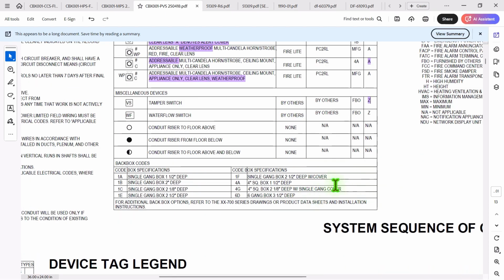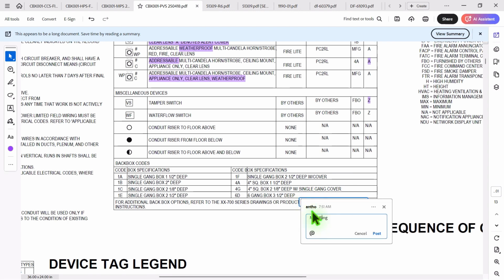Now when we get down to here, I'm not sure if we could add a mud ring into this to mount the pull stations. I'll show you a depiction of what that would look like, with a pull station mud ring onto a regular 1900 box, 2.5 regular size single gang box. But let's see if we can add the mud ring. Also a 4-inch round box for the smoke detectors, for the smokes and heat.